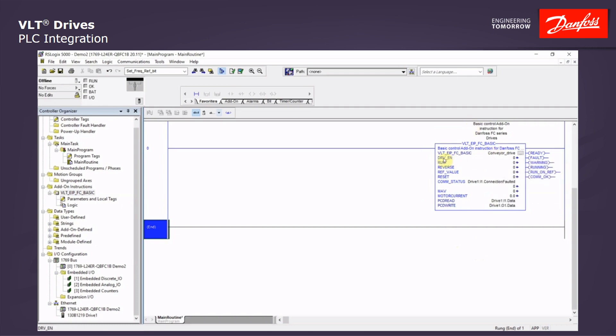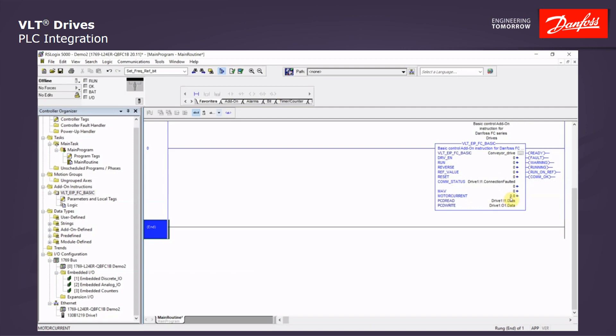This gives you, this is the enable the block itself. This will start and stop the drive. Reverse the drive. Give the drive a speed reference. This is in 0 to 100%. Give a reset to any alarms or warnings. We can see here a variable for the main actual value or the output percent the drive is running at and motor current as well as some binary data.